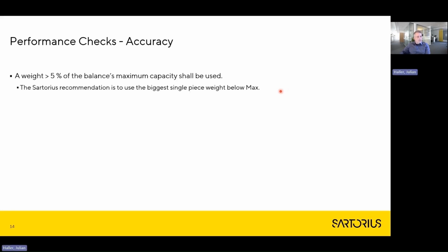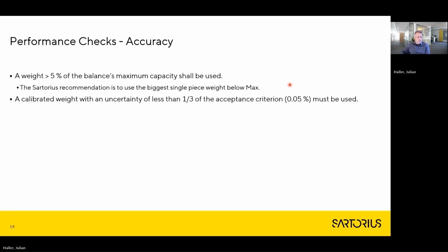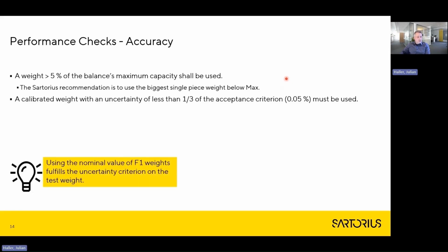The accuracy performance check should be done with a weight of more than 5% of the balance's maximum capacity. Our recommendation is to use the biggest single piece weight below the maximum capacity. A calibrated weight shall be used with an uncertainty of less than 1/3 of the acceptance criterion. And note, if you use a weight of class F1 according to OIML R111, and you use the nominal value, this requirement is fulfilled.